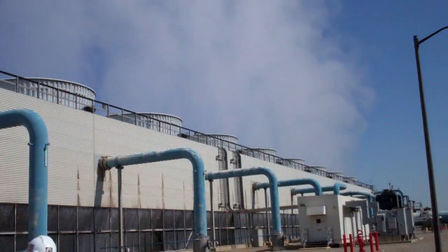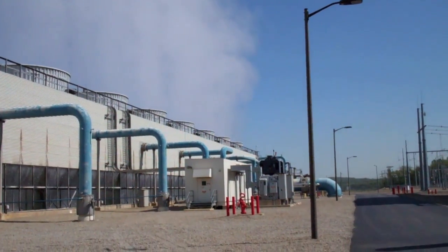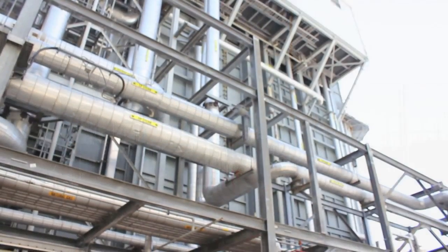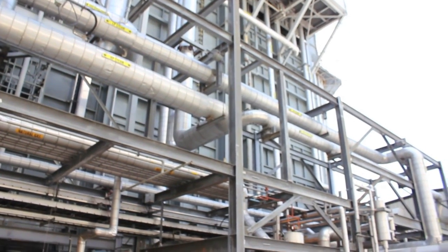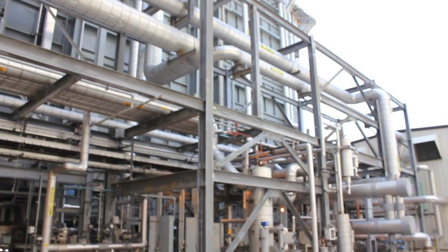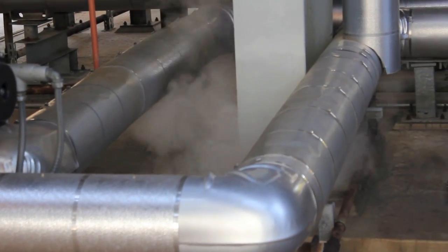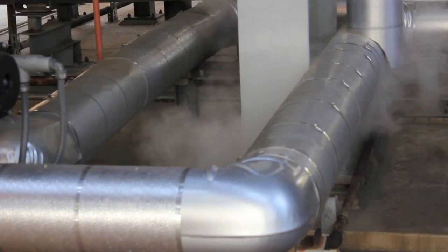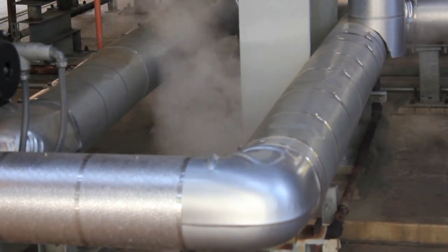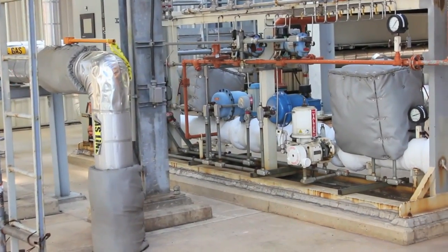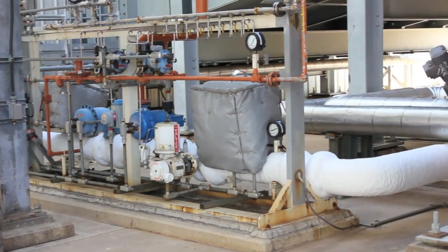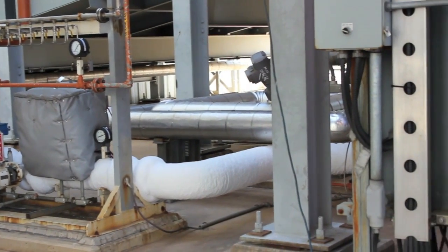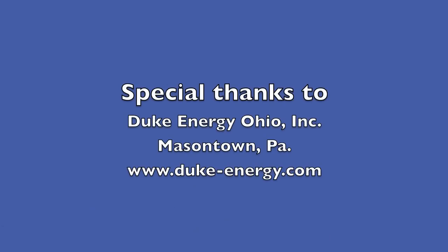That pretty much covers it. We've seen everything from the water treatment part of the facility, where really the life starts of a power plant, through the cooling tower, the switchyard, the different turbines and condenser that we have. We've seen the boilers and where the emissions control is done. We've seen the fuel source and our inlet chillers and duct burners, and I think that pretty much summarizes how a combined cycle power plant like ours operates.